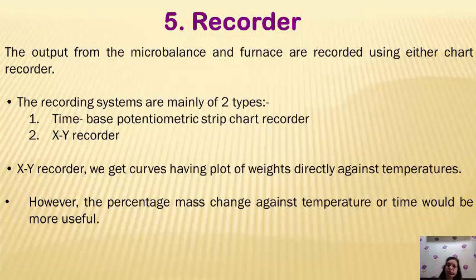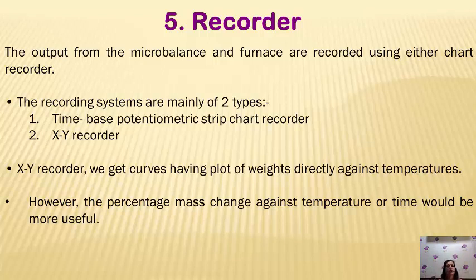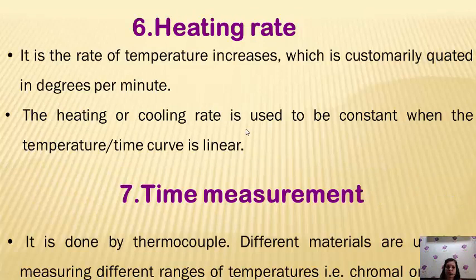The recorder: the output of the micro-balance and thermo-furnace are recorded using a chart recorder. The recording systems are mainly of two types: time-base potentiometric strip chart recorder and XY recorder. The XY recorder is more useful as you get a plot of weight directly against temperature. Nowadays there are advancements where you get percentage of mass change with respect to temperature too, without calculation, which is more useful.